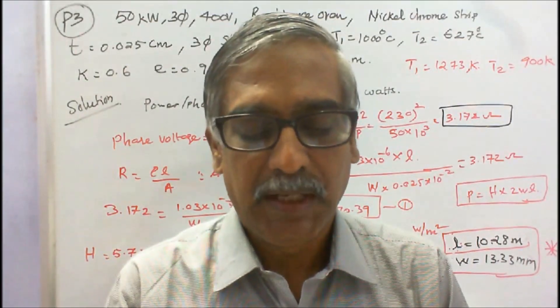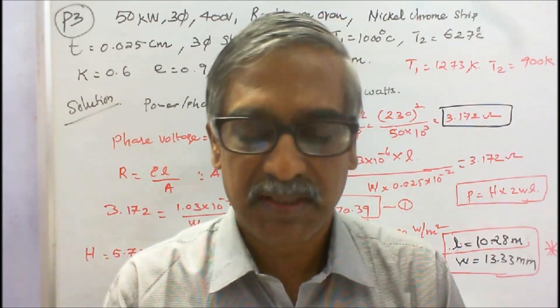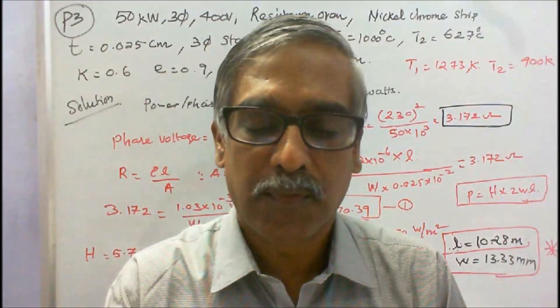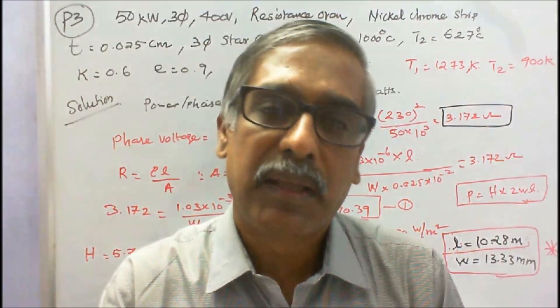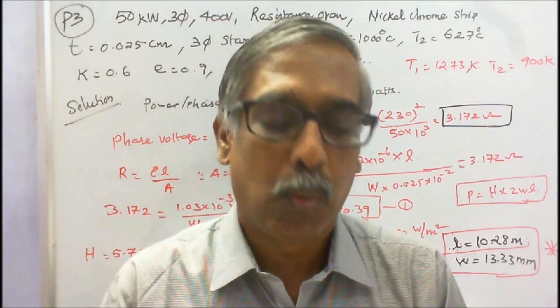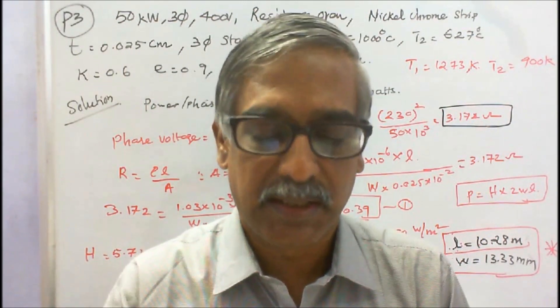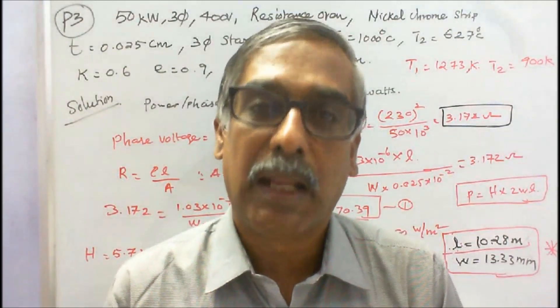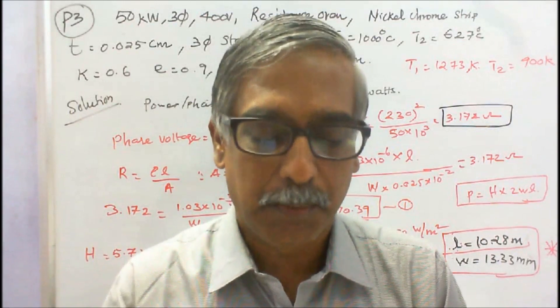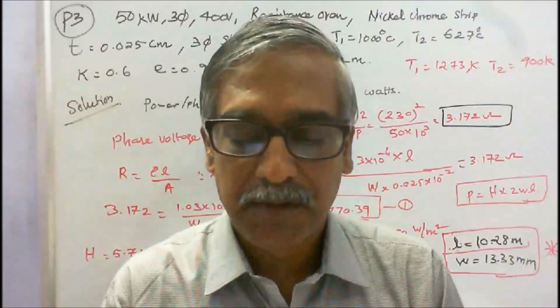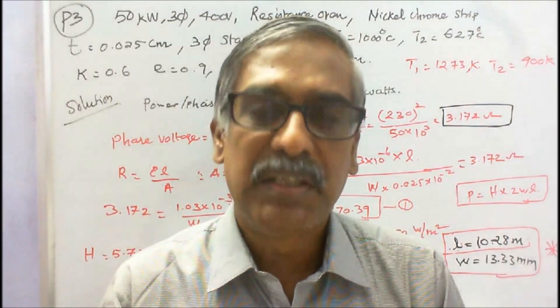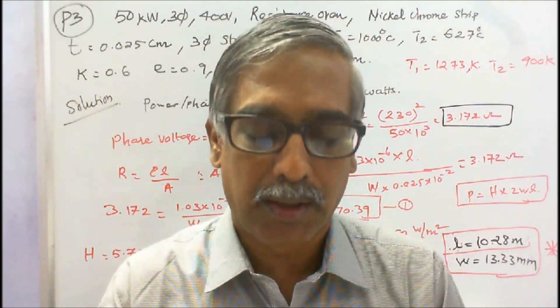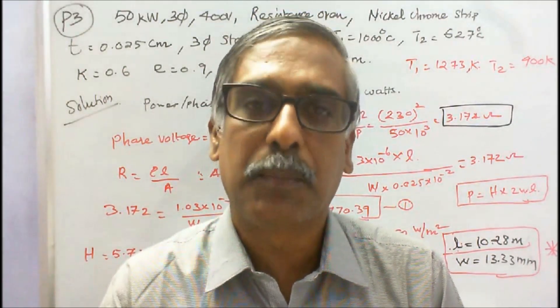Problem 3: Calculate the dimensions for a 50kW three-phase 400V resistance oven employing a nickel-chrome strip of 0.025 cm thickness for the three-phase star-connected heating element. If the wire temperature is to be 1000°C and that of the charge is to be 627°C, calculate a suitable width of the strip. Assume radiating efficiency is 0.6, emissivity is 0.9, and specific resistance of nickel-chrome alloy is 1.03×10⁻⁶ ohm-meter.